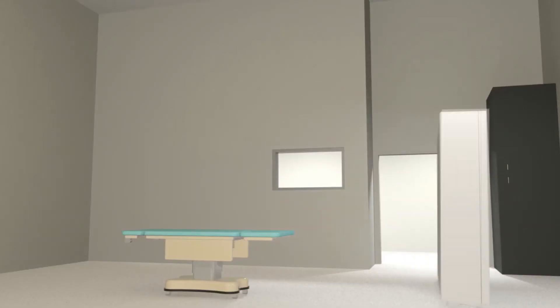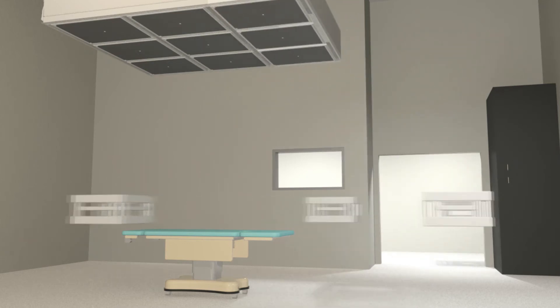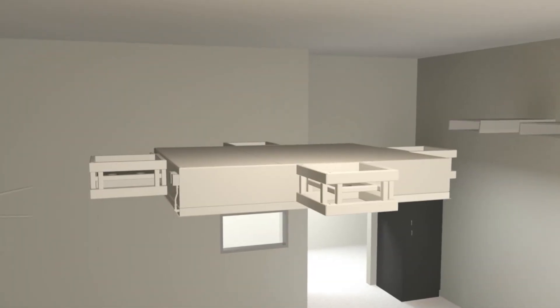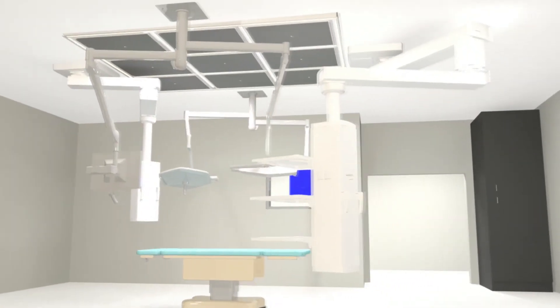From a Multiplex perspective, the primary lesson learnt for the project was to introduce the airframe at the earliest stage possible. The reason being you want the airframe team to be an integral part of your design and coordination process, making sure that high-level services coordination has already factored in the airframe as part of that process.